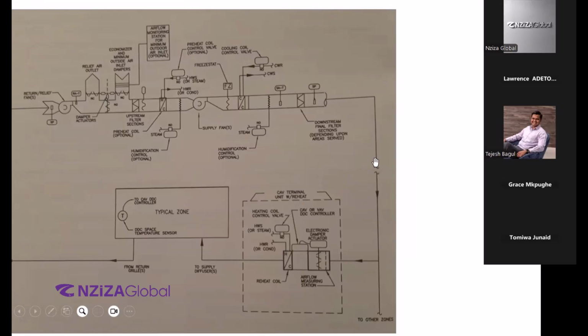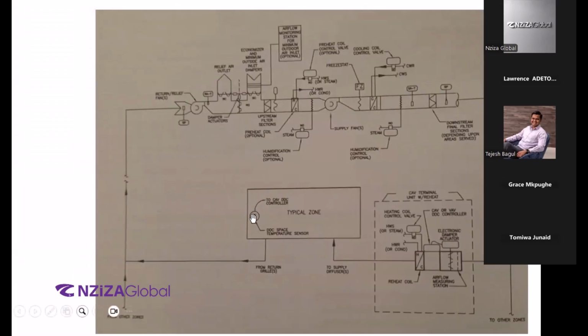All right. So even if the air is coming out at 15 to 16 degrees centigrade over here, and if you want to maintain a pretty 20 to 24 degree or whatever it is as per ASHRAE, you might need to heat it a bit more so that the leaving air temperature from here is adequate enough to meet the load of this area. We don't even want to introduce too cold of air in there, right? That is also not proper, because we also need heat to counter that cold air that we will be sending in. Make sense? Then we'll have the thermostat, which is maintaining the temperature of the given area. And this is where the return air will go back to the air handling unit.